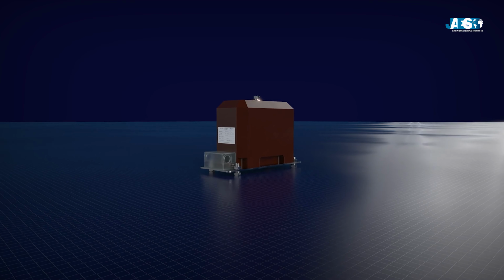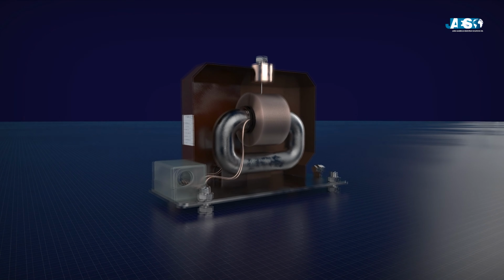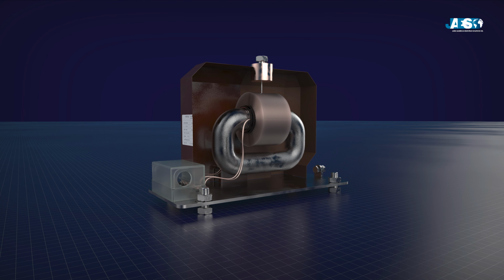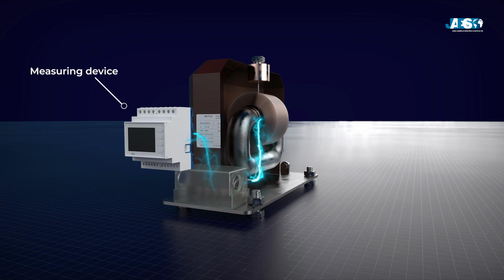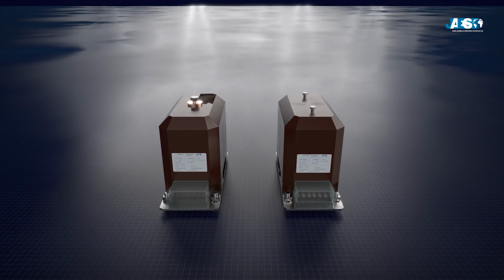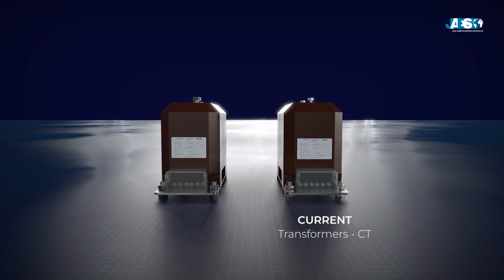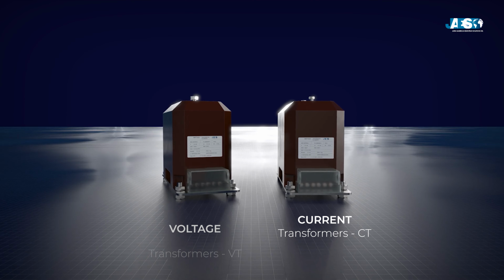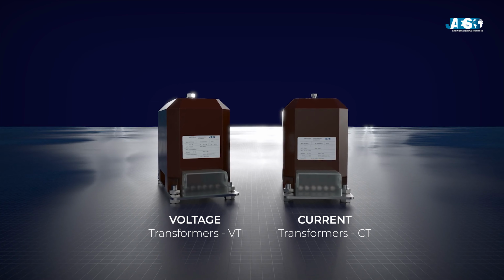Let's see how they're designed on the inside. The measuring transformer consists of a magnetic core and two windings, a primary and a secondary. The main current to be measured is passed through the primary winding, or the voltage to be measured is applied to the ends of the primary winding, while the secondary winding is connected to a measuring device, such as an ammeter or a voltmeter. The family of measurement transformers is divided into two macro categories: amperometric transformers, or CTs, and voltametric transformers, or VTs.